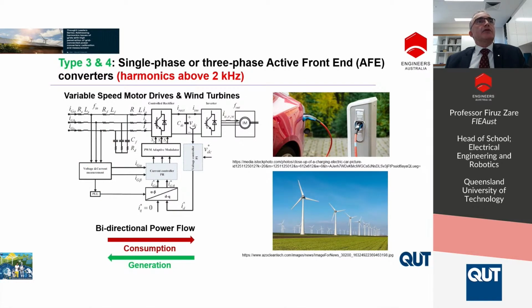The other types, type 3 and 4, are based on active in-feed converter technology, which is a bridge inverter, either single phase or three phase, combined with an LCL filter, and it has to be an LCL filter to make sure that high frequency ripple harmonics can be controlled. The main advantage of this topology is bidirectional power flow, which means it can be utilized for battery chargers, renewable energy, or different systems where the power can be generated to the grid or back to the device, depending on the system. For example, in a battery charger, if you want to charge the battery, we take the power from the grid, and if you want to feed back, we can transfer the power from the battery to the network.